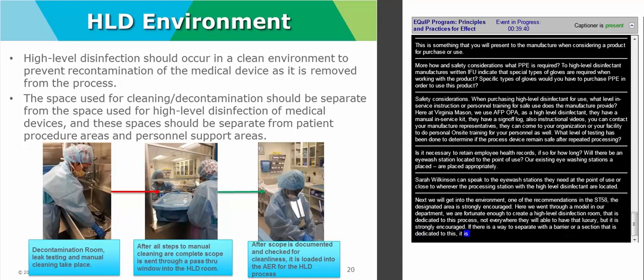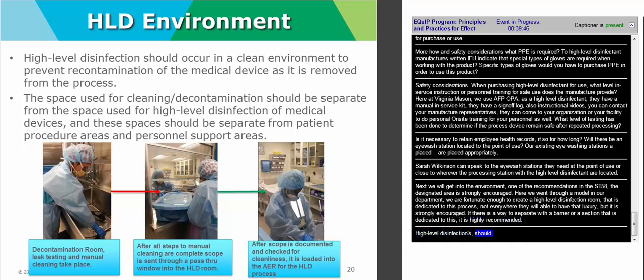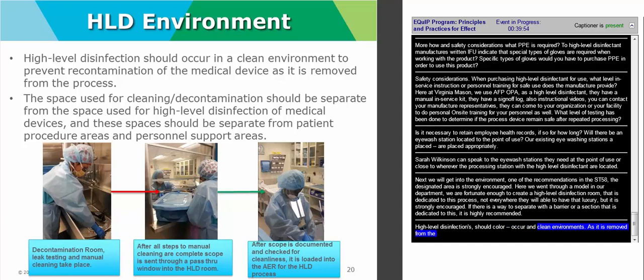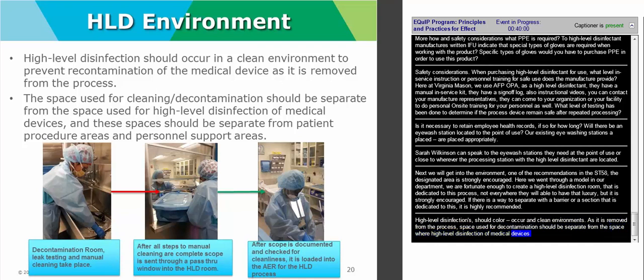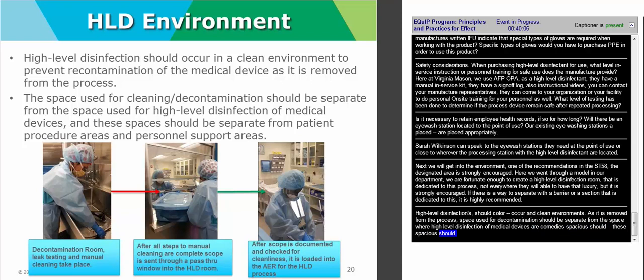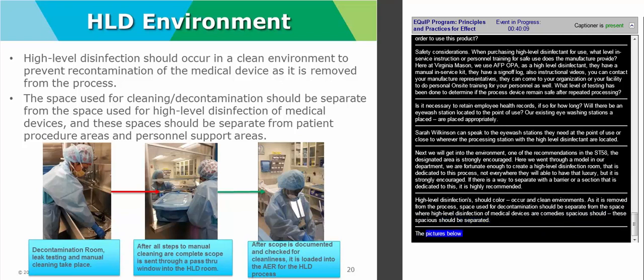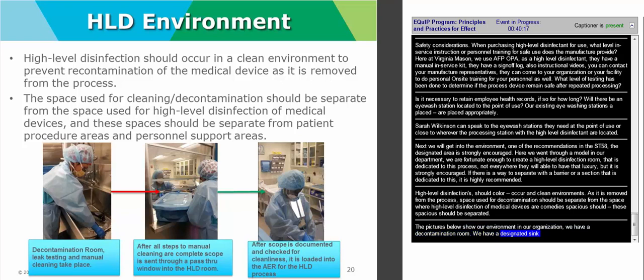High-level disinfection should occur in a clean environment to prevent recontamination of a medical device as it is removed from the process. So space used for cleaning and decontamination should be separate from the space for high-level disinfection of medical devices. These spaces should also be separated from patient procedure areas and personnel support areas. The pictures below show what our environment looks like here in our organization. We have a decontamination room that has a dedicated sink for cleaning flexible endoscopes and the anesthesia equipment that the technicians handle for the high-level disinfection process.